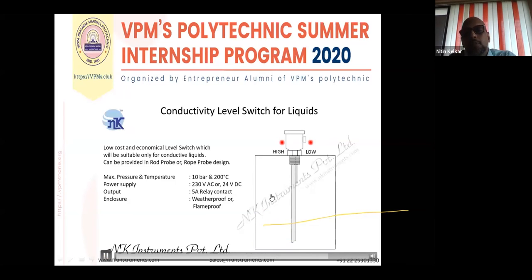In that case, the metallic tank body itself operates as a reference for this probe. If the tank is non-metallic, if it is PVC or some plastic tank, in that case the reference probe is compulsory. So reference, low level switch, high level switch, sometimes people require a mid level switch, or it can be low, low-low, high and high-high, 4 level switches. So depending on that, the number of probes can be increased.